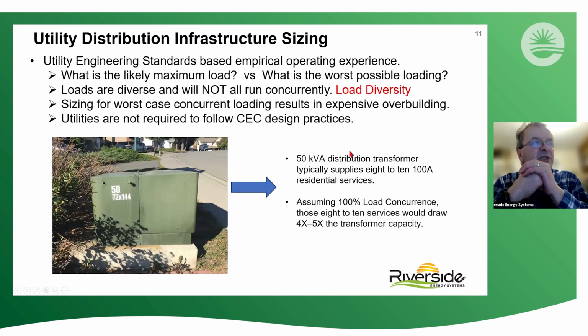So it turns out that utilities size their infrastructure using engineering standards. They look at what is the likely maximum load. They don't look at what the worst possible scenario is. They assume that loads are diverse and they will not all run concurrently. In other words, they're assuming load diversity. So we have these two paradigms, CEC safety, which assumes load concurrence, and utility practical engineering standards, which assume load diversity. And those two butt heads. In fact, if a utility was forced to size their transformers to meet 100% load concurrence, this 50 kVA pad mount transformer that serves 8 to 10 100 amp residential services would have to be 4 or 5 times the size. So, and we know they're not, and the reason they're not is because they don't need to be.